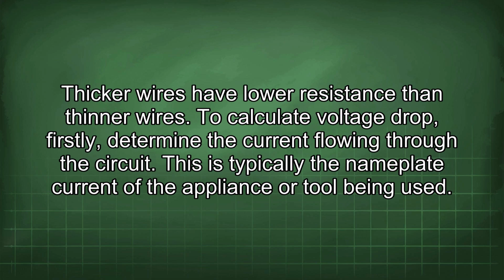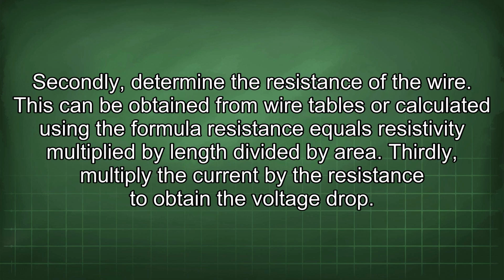To calculate voltage drop, firstly, determine the current flowing through the circuit. This is typically the nameplate current of the appliance or tool being used. Secondly, determine the resistance of the wire. This can be obtained from wire tables or calculated using the formula resistance equals resistivity multiplied by length divided by area. Thirdly, multiply the current by the resistance to obtain the voltage drop.